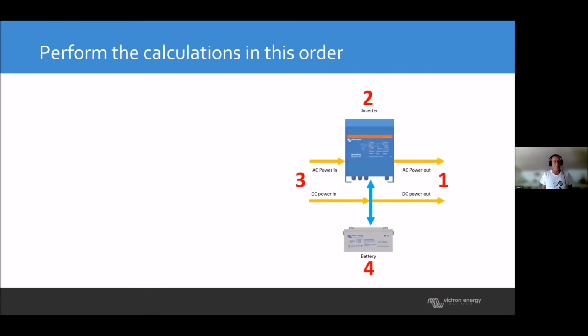Calculation on some parts is easy, but for a lot of people it's not so easy. The first thing you need is to know how much consumption you have, both in kilowatt and in kilowatt peak, from the inverter, so you can be sure the inverter system is big enough. Next, is there any grid or generator connected? The system must be able to handle that. And finally, we need to calculate how big the battery bank must be to serve the system people are asking for.